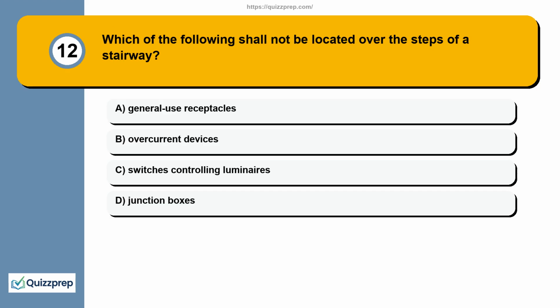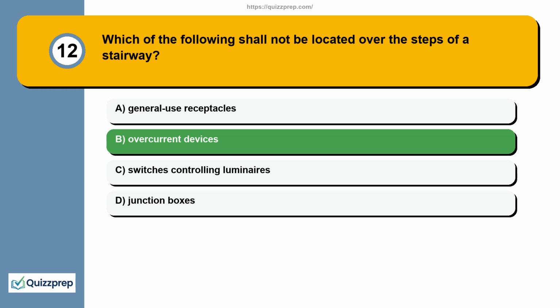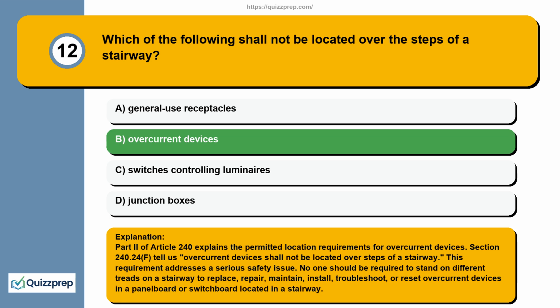Question 12. Which of the following shall not be located over the steps of a stairway? General use receptacles, overcurrent devices, switches controlling luminaires, junction boxes. Part 2 of Article 240 explains the permitted location requirements for overcurrent devices. Section 240.24 f tells us overcurrent devices shall not be located over steps of a stairway.